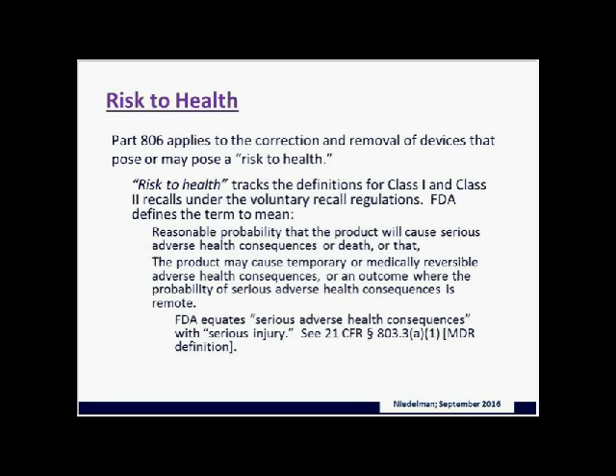Again, based on the regulation, if you report a removal or correction under the MDR reporting requirements or under the radiation, the electronic products reporting mechanism, you in theory don't have to submit a separate corrections and removals report. We encourage you to submit it anyhow. These often get lost in transition, and before you know it, FDA is on you for not reporting, and then you have to explain why you didn't report. It's just easier and safer that you report those to the district in a timely manner.